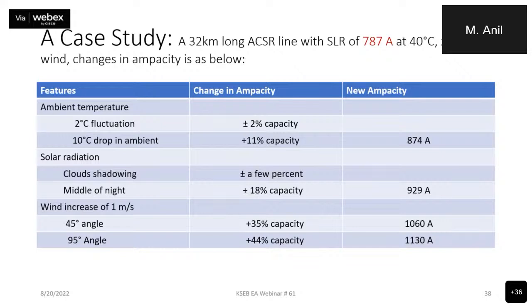So, a wind increase of 1 meter per second. If the wind direction is 45 degrees, then plus 35% capacity enhancement can be achieved, resulting in an enhancement from the SLR of 787 amperes to a DLR of 1060 amperes. Similarly, with a 95 degree wind direction, 44% ampacity enhancement can be achieved, with a change in ampacity from the SLR of 787 ampere at 40 degrees Celsius to 1130 amperes.